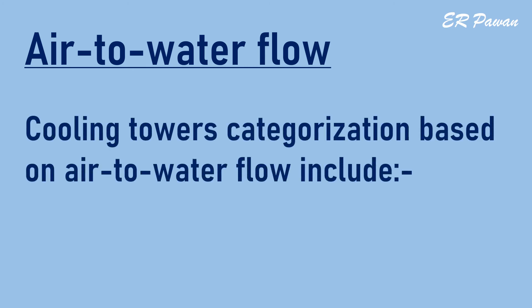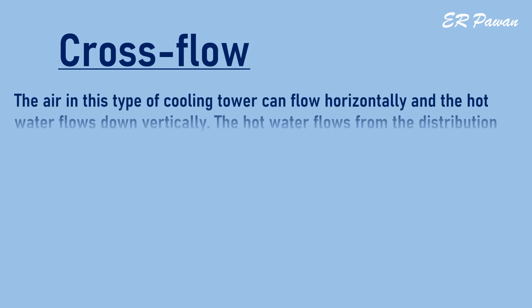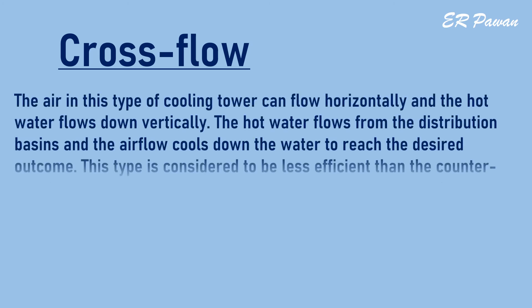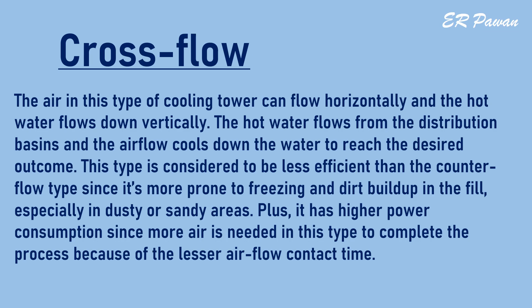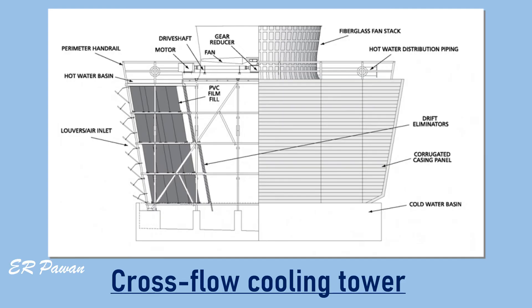Air-to-water flow categorization includes cross flow and counter flow. Cross flow: in this type, the air flows horizontally and the hot water flows down vertically from distribution basins, and the airflow cools the water to reach the desired outcome. Cross flow is considered less efficient than counter flow since it is more prone to freezing and dirt buildup in the fill, especially in dusty or sandy areas. It also has higher power consumption since more air is needed due to the lesser airflow contact time.